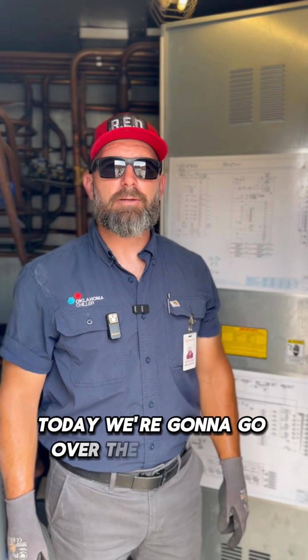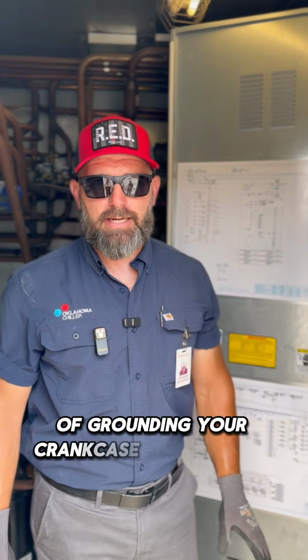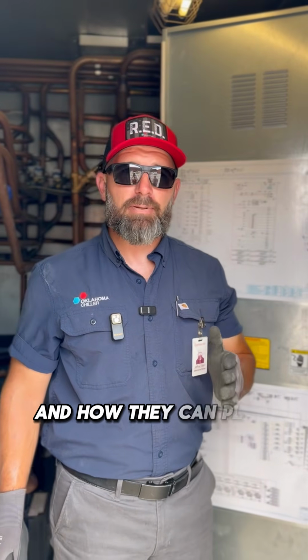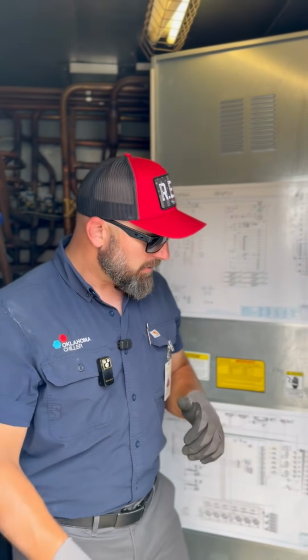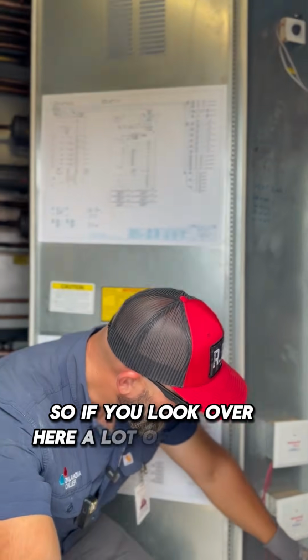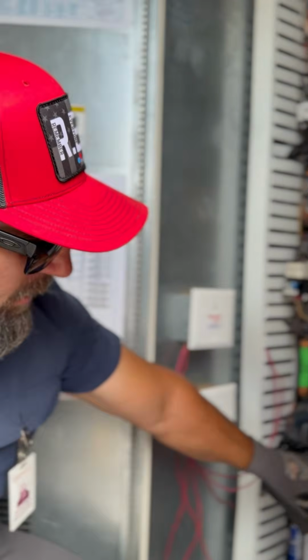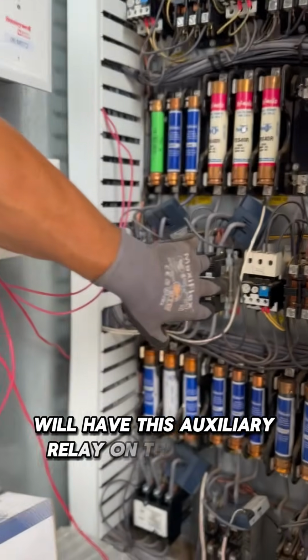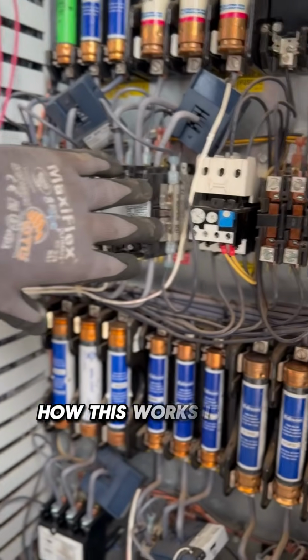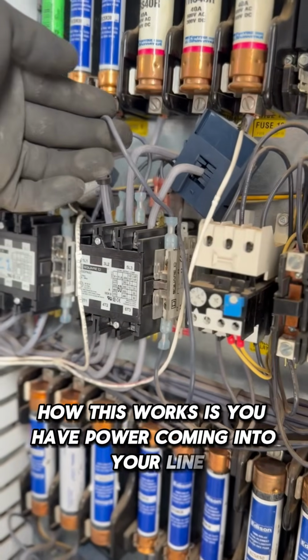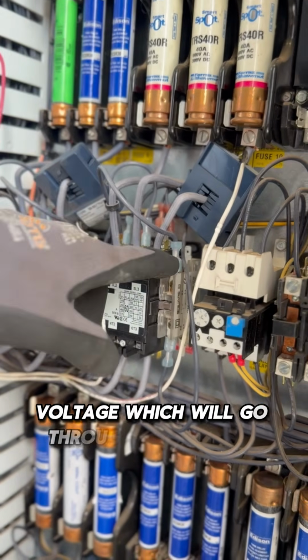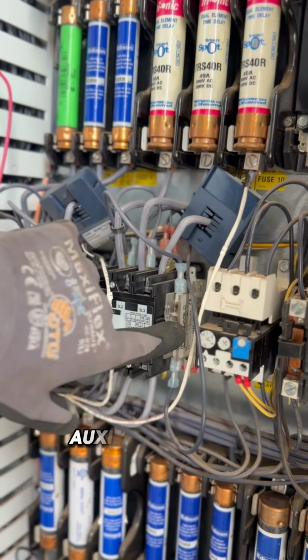Today we're going to go over the importance of grounding your crankcase heater strips and how they can play into a failed compressor. So if you look over here, a lot of your main compressors will have this auxiliary relay on the side here. How this works is you have power coming into your line voltage, which will go through a normally closed auxiliary switch.